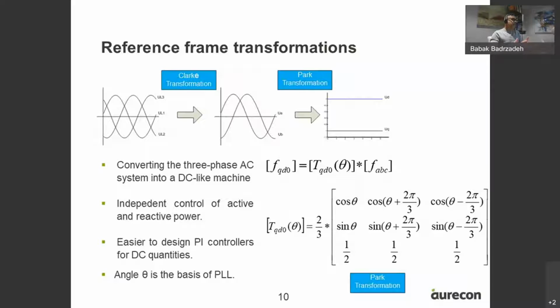The advantage is that control of active and reactive power can be done largely independently, without interfering with each other, thanks to the Park and Clarke transformations. Park transformation is the more general one; setting the angle theta to zero reduces it to the Clarke transformation, which is what we have here. What is the importance of this angle? Essentially, determining it is the job of the phase lock loop, or PLL, which performs this task and instructs the rest of the control systems within the inverter control.